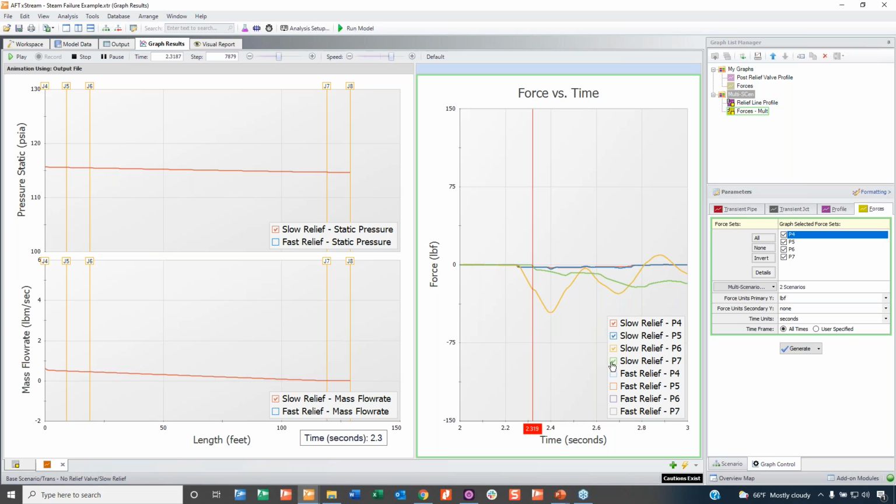The exit is still larger than that. It's a little different story just because now you're at a boundary and that force is just blowing that opening completely out. But it's still larger in magnitude than that. So again, it's about that pipe length. So here, valve opening makes a huge difference in my system responses as far as forces go.